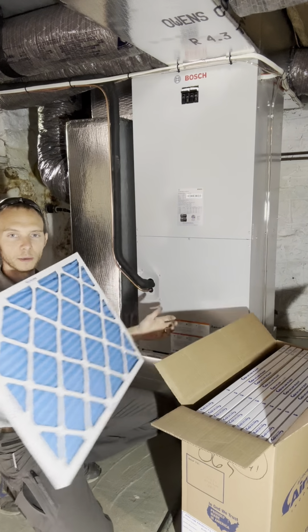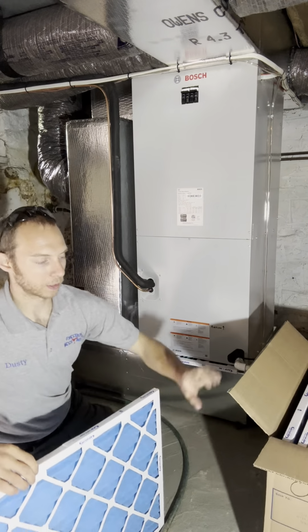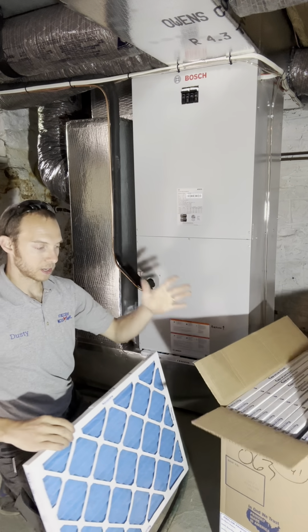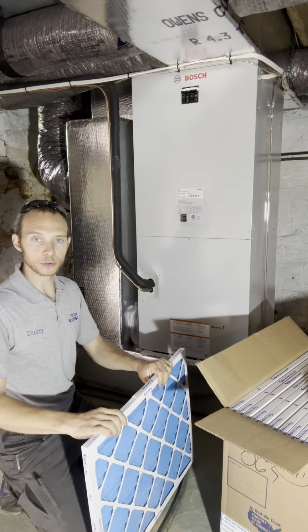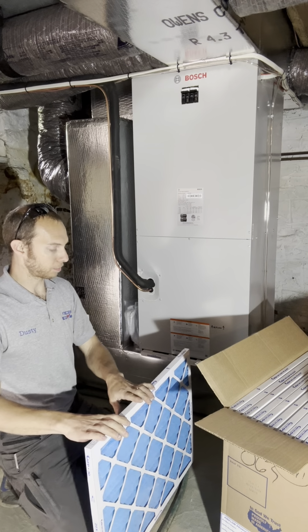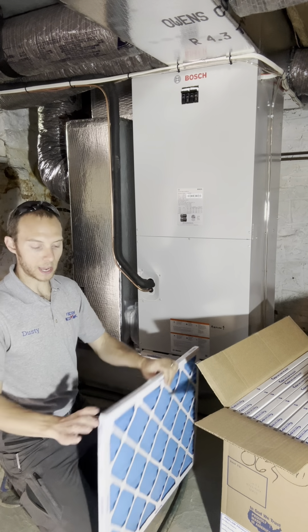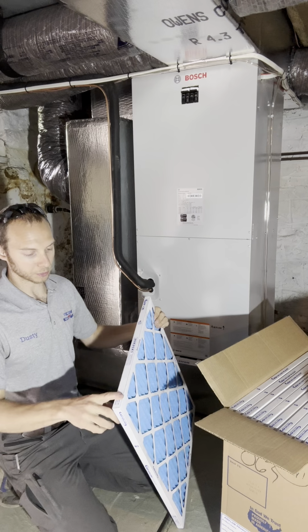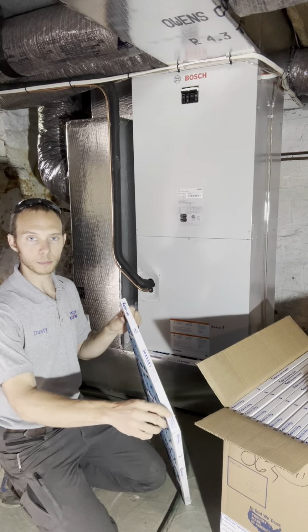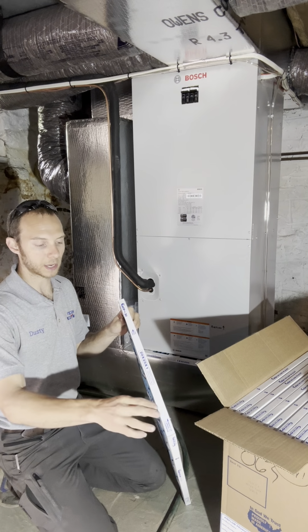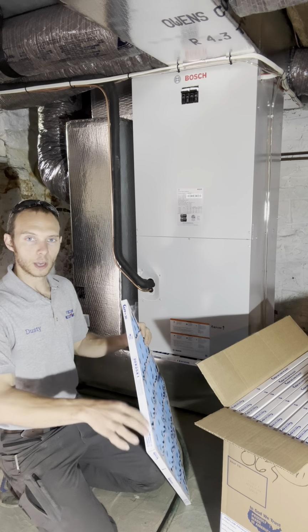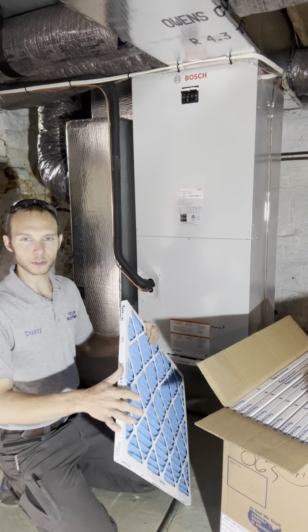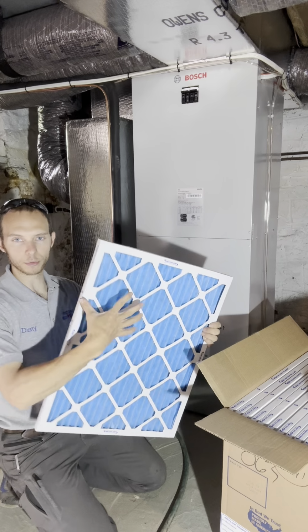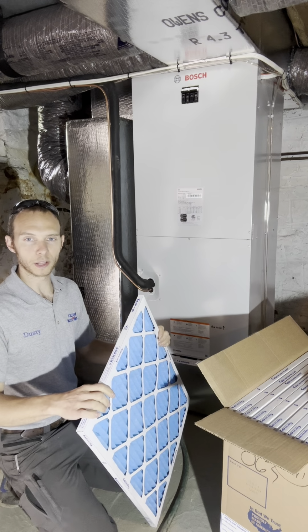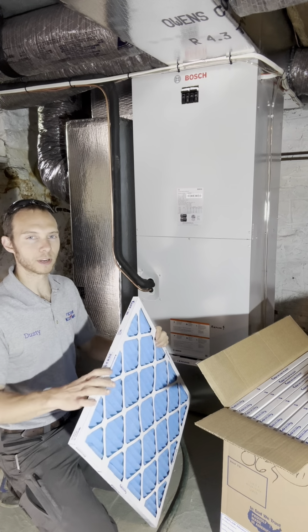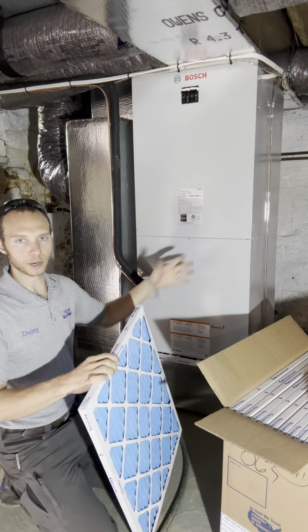Now, we typically provide a box, or at least the option to get a box of air filters with a new system. What we typically provide is a MERV 10. So a lot of these filters have a MERV rating hiding on them. If you're buying them on Amazon or something like that, you want to check your MERV rating. A MERV, I think it's 5 or something like that. You can see straight through them. They're basically a fiberglass mesh. So they're not going to provide a whole lot of protection for this brand new coil.